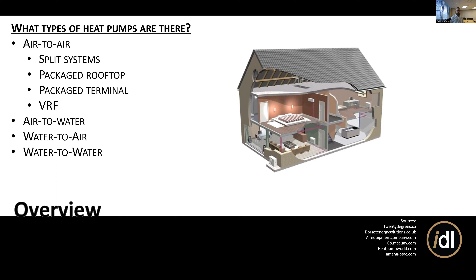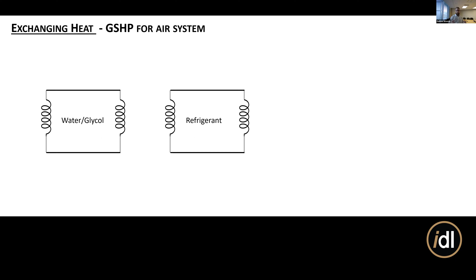Or we could link it with a hydronic system, a radiant system, and that might take an extra loop. So when we're talking about the different loops that are involved with the ground source heat pump system, what's buried outside is going to be some sort of water, brine or glycol mixture, antifreeze basically, so it doesn't freeze up in the pump. And then this refrigerant line is separate from it, and that's going to be contained within the heat pump itself.